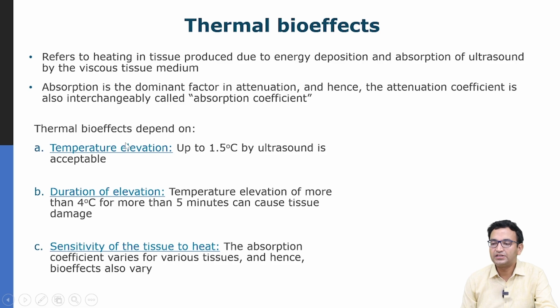Now, the temperature bioeffects depend on the temperature elevation. For example, if I take a certain tissue region and I am doing imaging, there will be heat deposition and therefore there will be temperature elevation. But if the temperature elevation is less than 1.5 degrees, then it is considered acceptable and low risk. However, if the temperature elevation is more than 4 degrees for more than 5 minutes, it can cause tissue damage, and it may be considered sensitive for regions such as the fetus, which are extraordinarily sensitive.